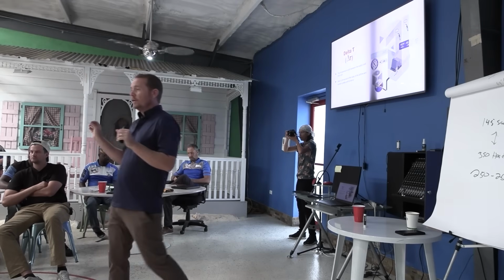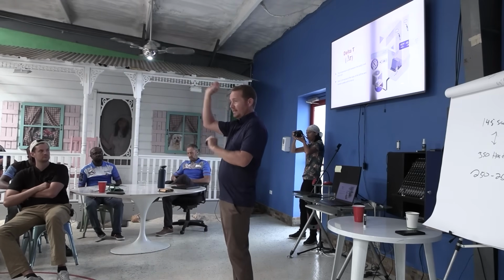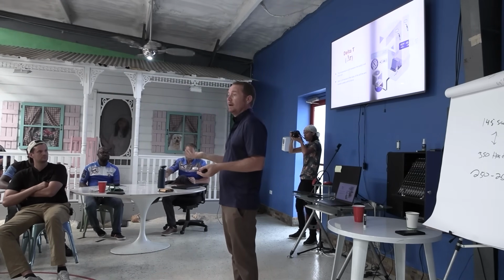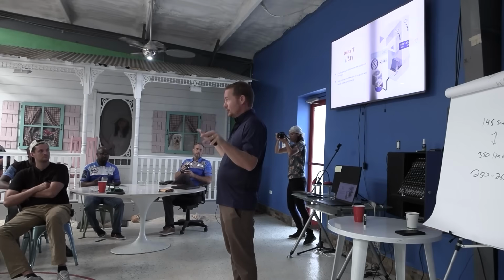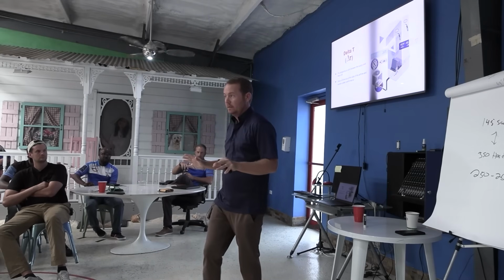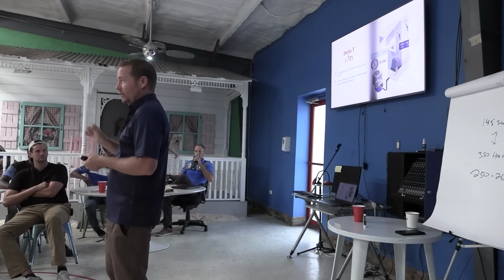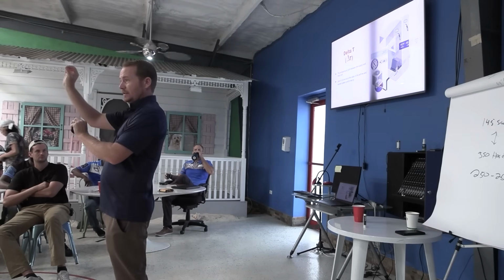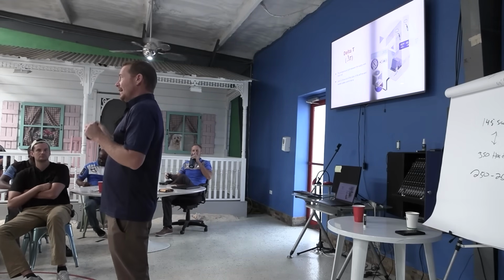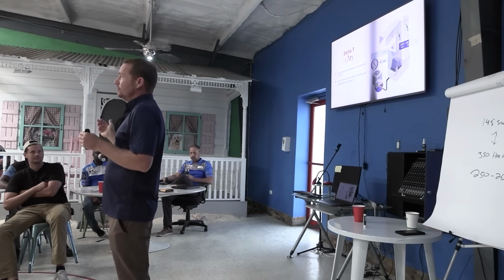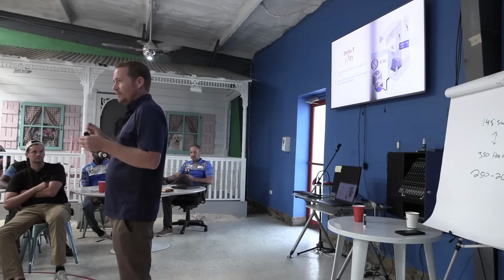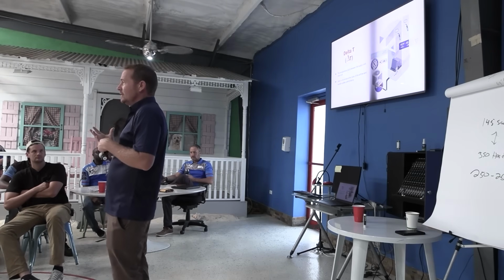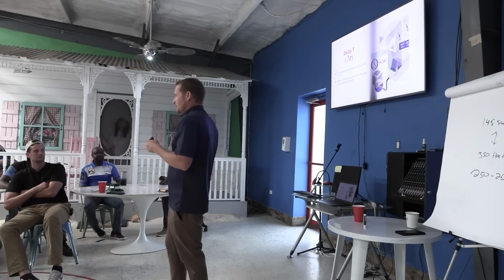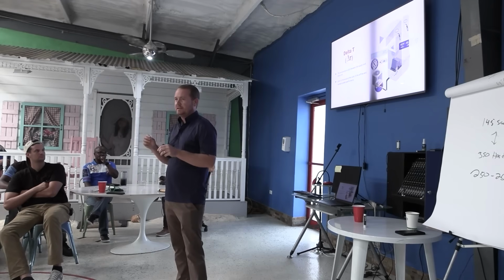Now what I would prefer is that you use a psychrometer in the supply and the return, because that would tell you a lot more. You'd be able to know how many BTUs you're moving. That's a better thing, and it's not that much harder, the hole's just a little bit bigger. Stick those in. The downside to psychrometers is the sensors are a little more sensitive, they're more expensive, so I'm still okay with people doing good old-fashioned delta T in and out.